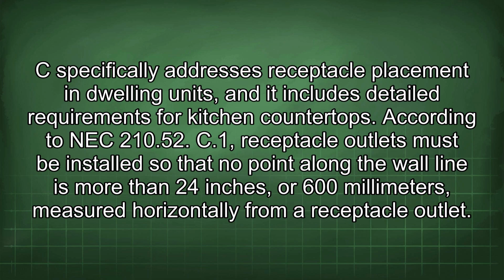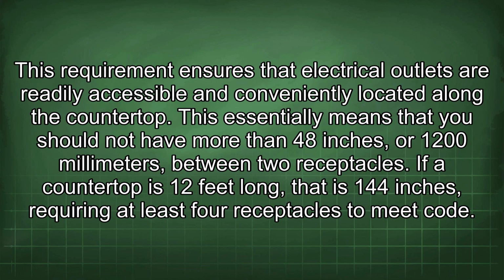According to NEC 210.52(C)(1), receptacle outlets must be installed so that no point along the wall line is more than 24 inches, or 600 millimeters, measured horizontally from a receptacle outlet. This requirement ensures that electrical outlets are readily accessible and conveniently located along the countertop. This essentially means that you should not have more than 48 inches, or 1200 millimeters, between two receptacles. If a countertop is 12 feet long, that is 144 inches, requiring at least 4 receptacles to meet code.